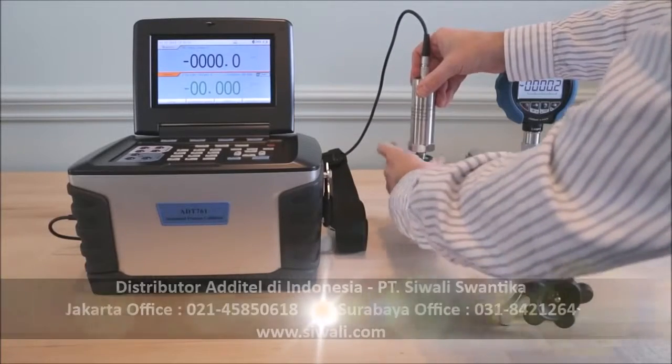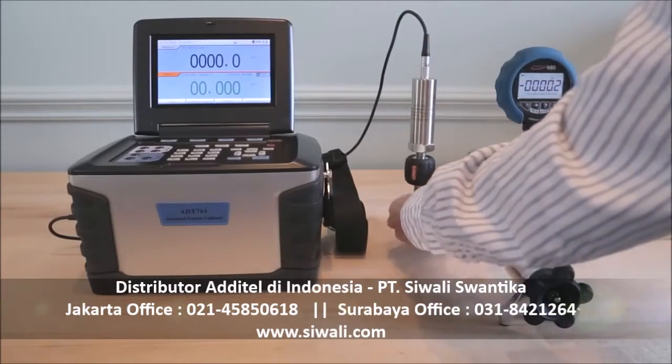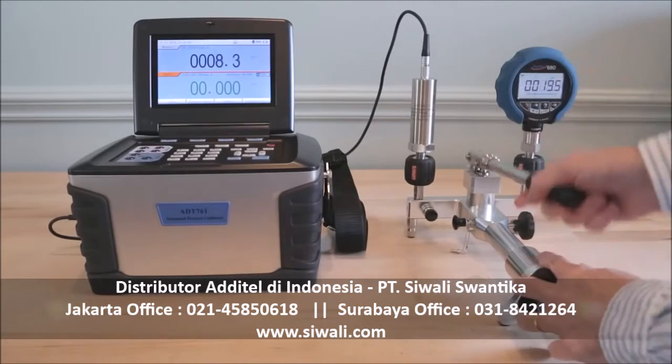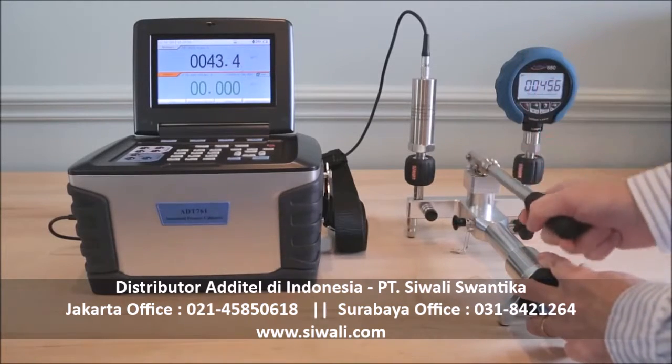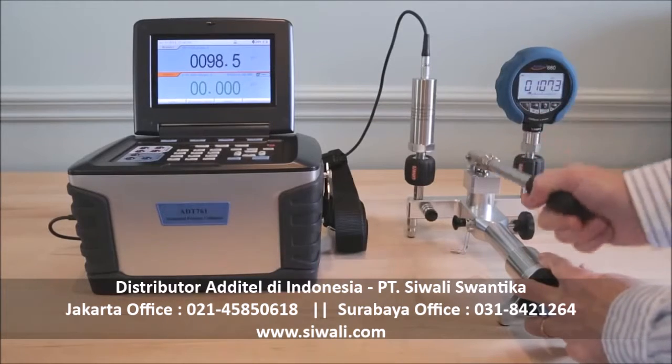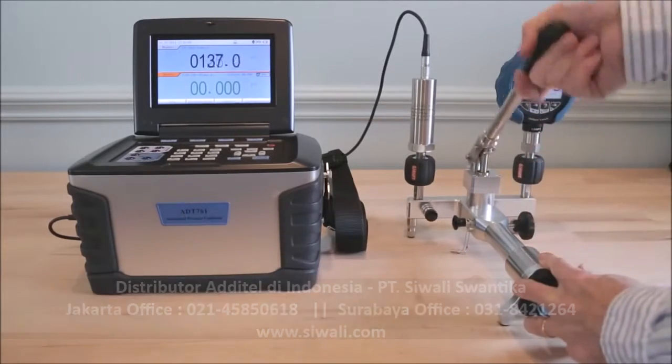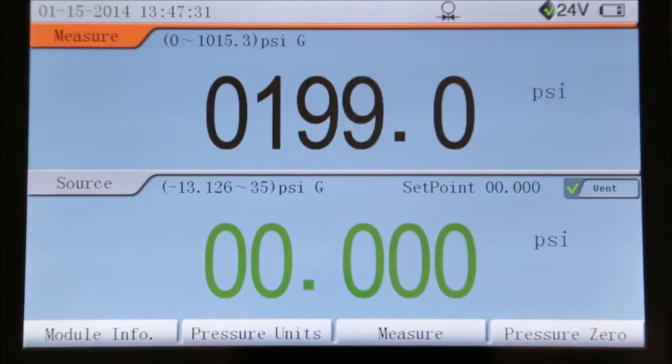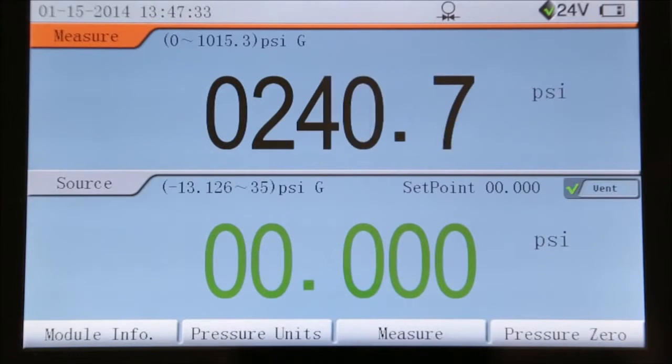With optional external pressure modules, the 761 can measure pressures up to 10,000 PSI with 0.025% accuracy. External pumps can be used for generating pressures above the 761 range and pressures can be displayed on the 761 screen.